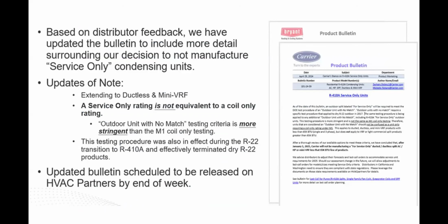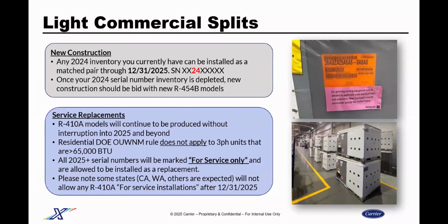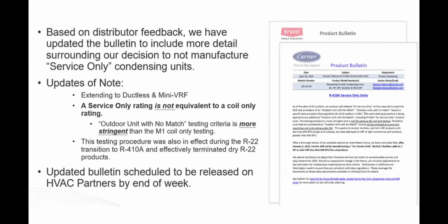There is the opportunity for a manufacturer of equipment to go ahead and produce what's called a service-only condensing unit, where they can continue making a 410A condensing unit this year and indefinitely with no end date, as long as they wish. However, there's a couple of caveats to that. One, it has to be specifically labeled for service only. So there's little pink tags all over the place saying this is for service only. It'll have a slightly different part number than we normally would have. But with that being said, pretty much no manufacturers are doing this.